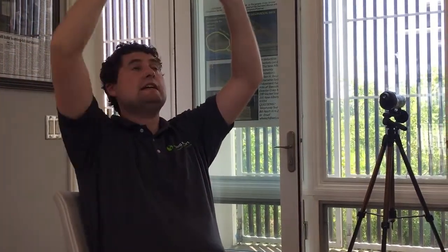So when we reassembled it, I came in and reconnected all of the controls in the house. Upon electrical inspection, because this house splits into 3 sections, there's a bunch of junction boxes above the ceiling. When the inspector came in, he said, rightfully so, that to have a junction box in the ceiling you have to have access to it. Because we had so many junction boxes up there for all the low voltage wiring for the control system, we basically would have ended up with access panels, probably 6 or 7 above my head and another 4 on the other side. It really would have, in my opinion, hurt the aesthetics of the building.